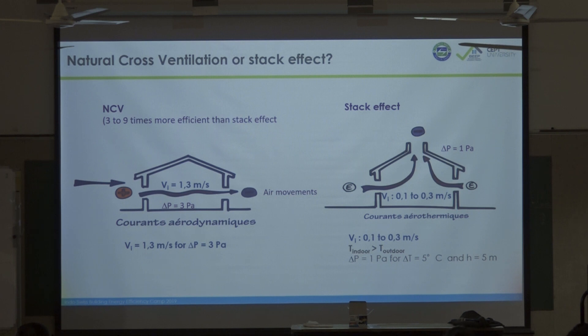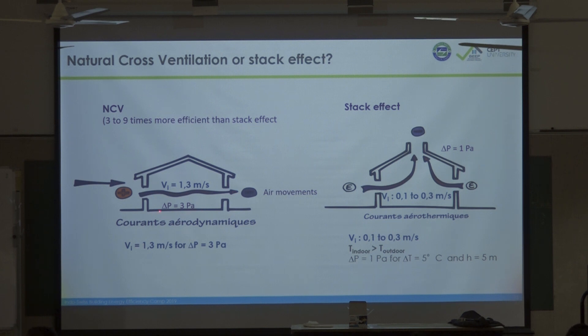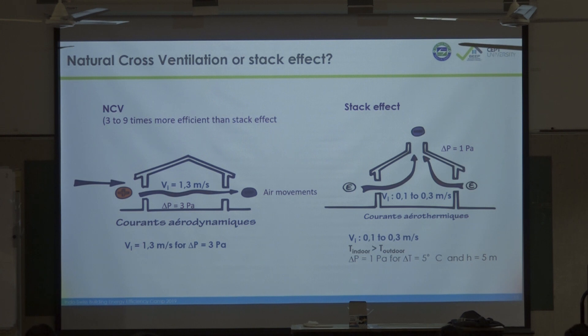Now we focus inside the building. First, a comparison between natural cross ventilation and the stack effect. If you can create a difference of pressure of 3 Pascals, you can generate a velocity of 1.3 meters per second — and 3 Pascals is a very low value compared to atmospheric pressure of 101,325 Pascals.